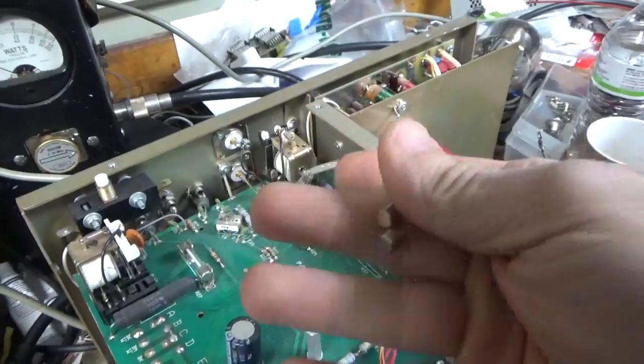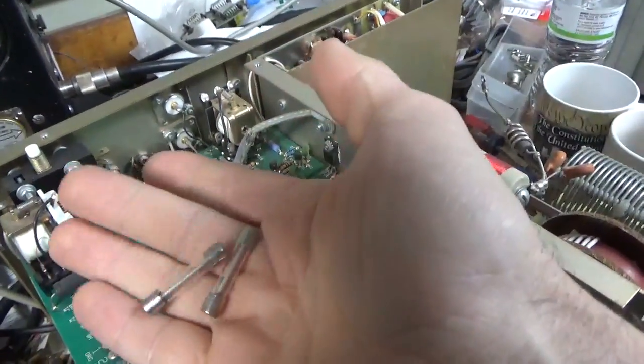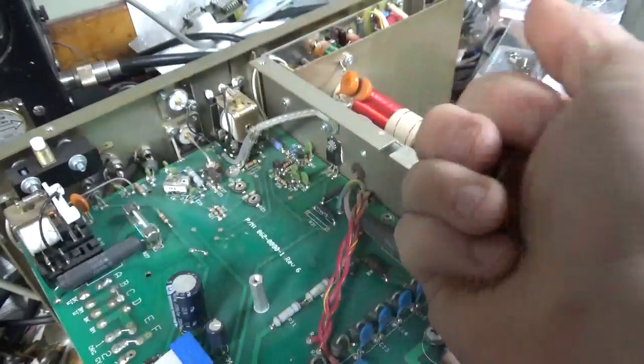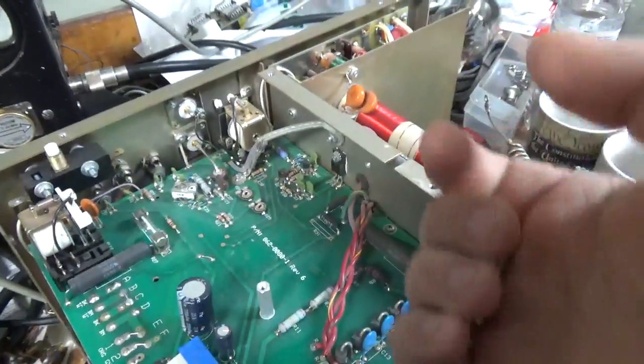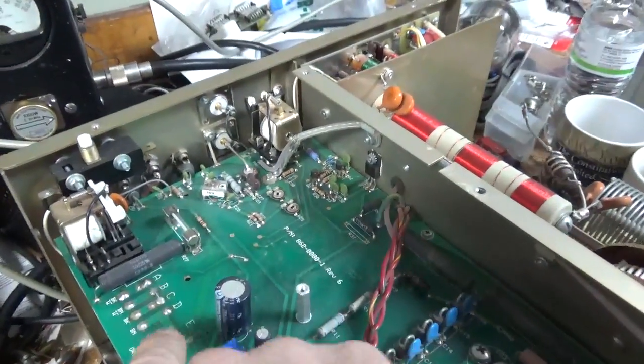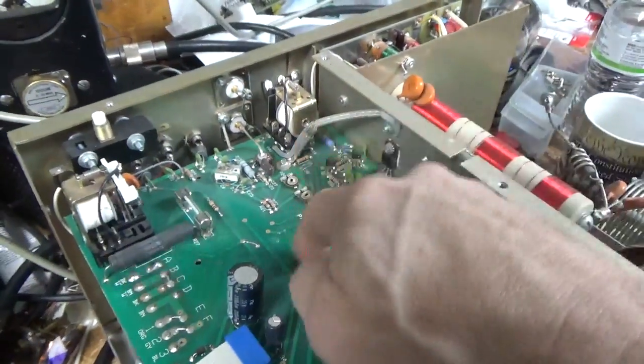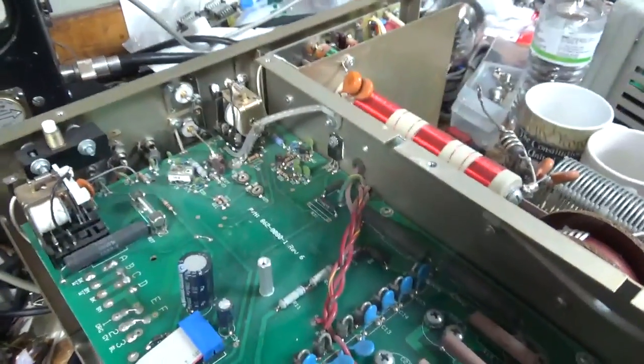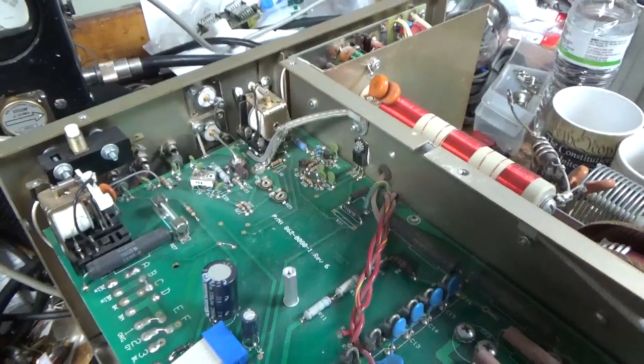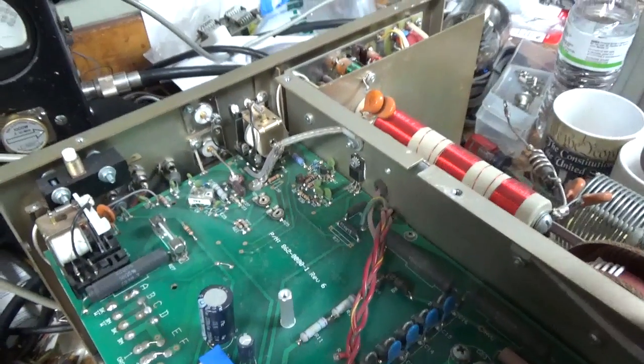When it's on 240, it gets 10 amp fuses. It actually has 10 amp slow blow fuses, but they're supposed to be fast blow. It's really critical to have the proper size fuse and the buck boost set properly, because you don't want to take out the plate transformer if you have a short on one of the secondaries.